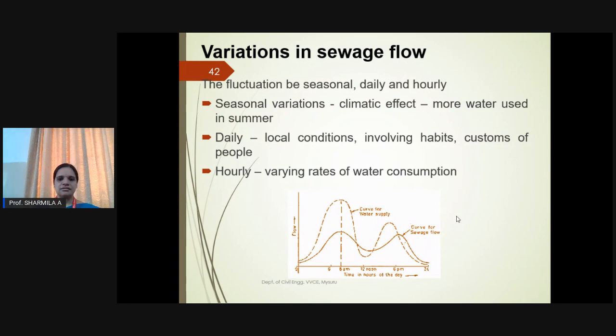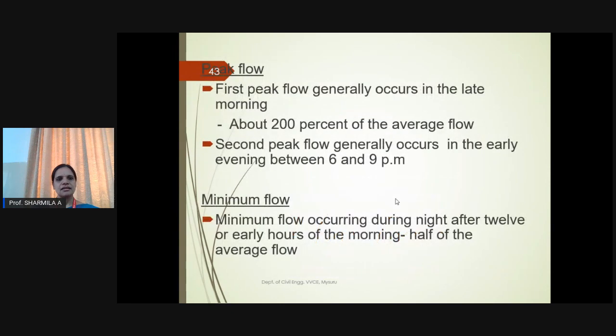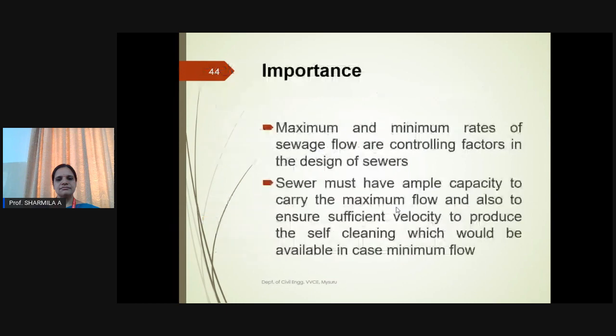Variation in sewage flow occurs on a daily basis. Fluctuation can be seasonal, daily, and hourly. Seasonal variation: due to climatic effects, more water is used in summer. Daily: local conditions involving habits and customs of the people. Hourly: varying rates of water consumption. Peak flow: the first peak generally occurs in late morning — about 200% of average flow — and the second peak in early evening between 6 to 9 PM. Minimum flow occurs during nighttime.